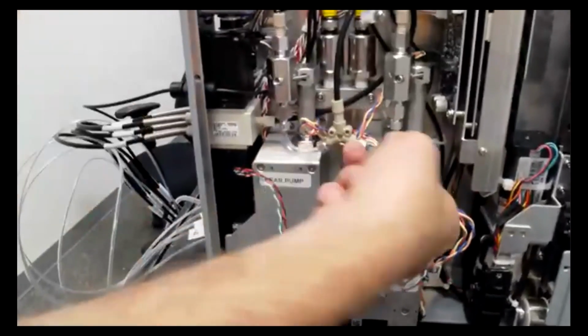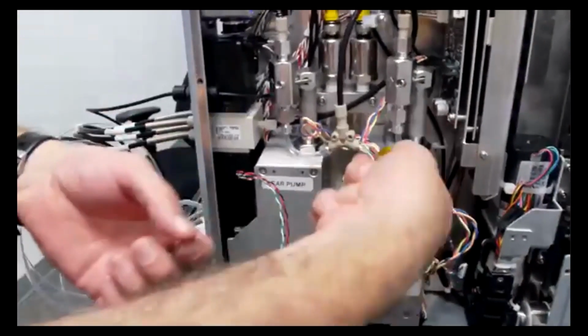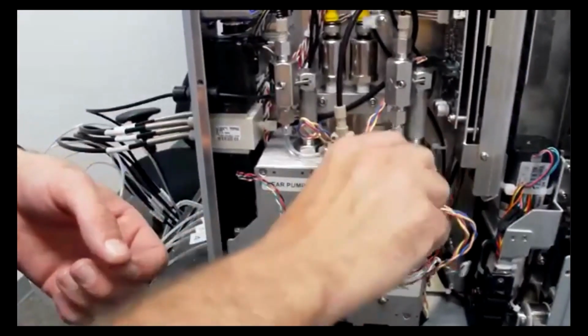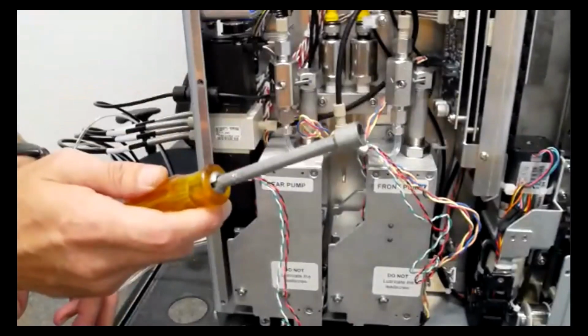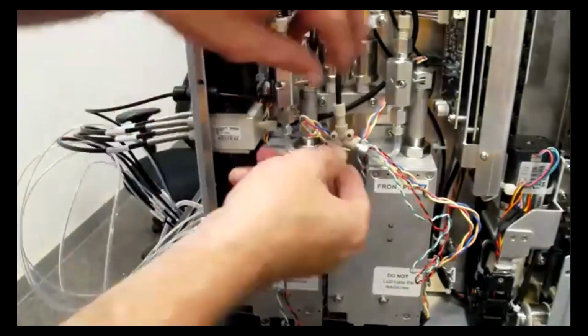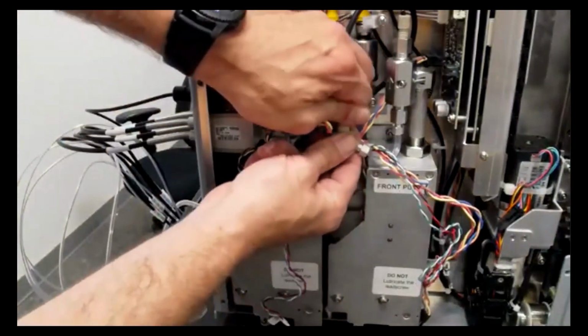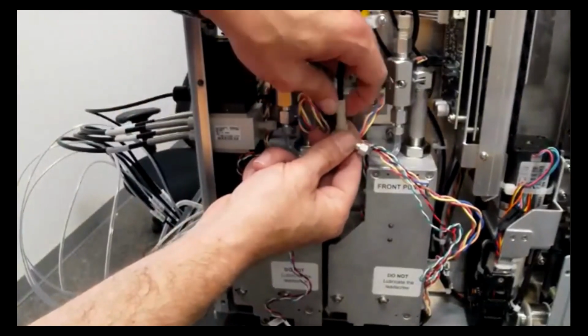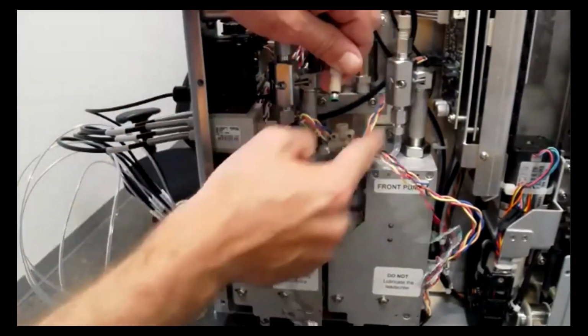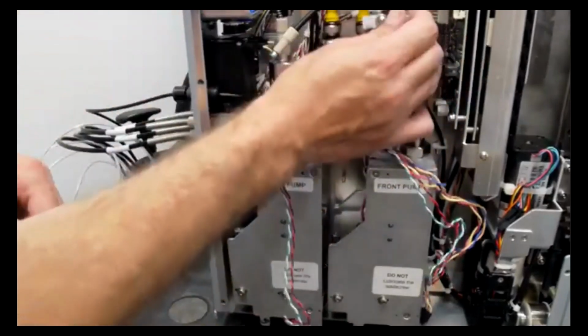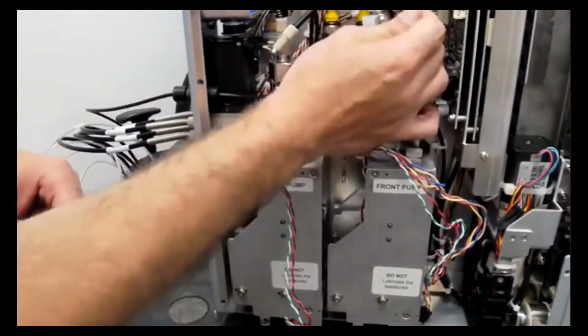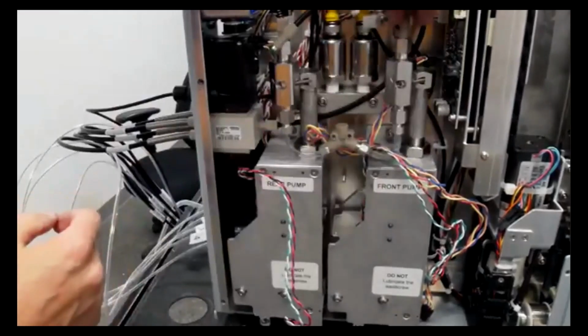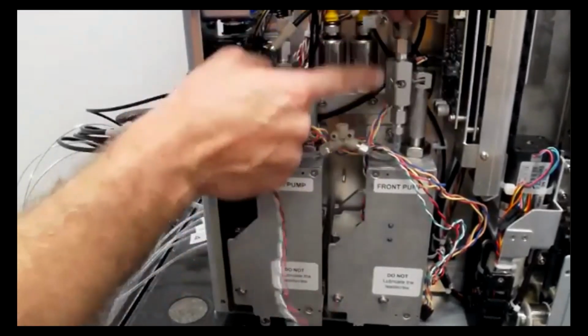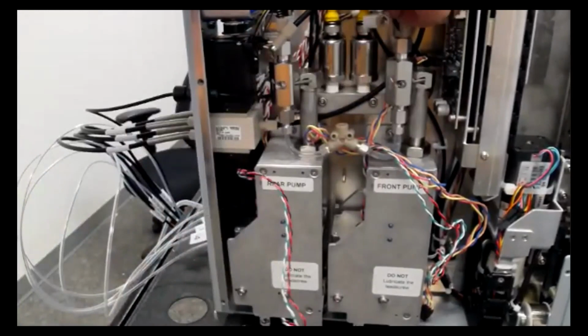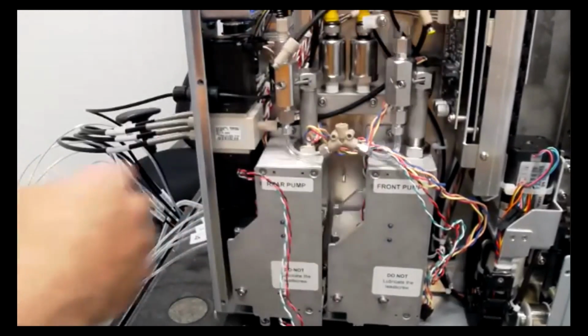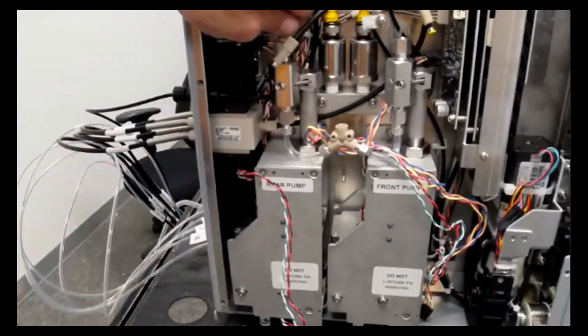Okay. So now I'm on the top nut. I'm gonna go ahead and loosen it a couple times. But before I go much further than that, I'm gonna remove this tubing line right here that goes to this union. And I'm going to remove the tubing lines that go to the top of the pump. This is the check valve housing. The arrow is pointing up towards this tube. Okay. I'm going to remove both of them as well.